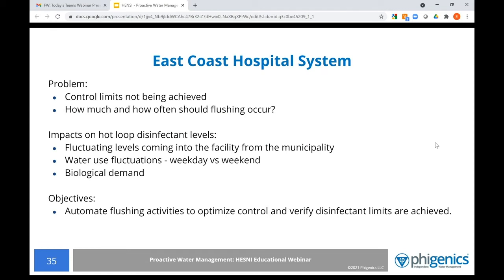Some of those impacts, especially within a hot loop, might include fluctuating levels coming from the municipality. Water use fluctuations is a big one. Maybe a facility uses more water on a weekday versus the weekend. And then biological demand will consume the disinfectants at different rates throughout the system. So our objective for this project was to automate the flushing activities to optimize our control and verify that those disinfectant control limits were being achieved.